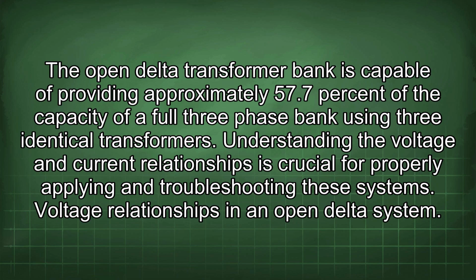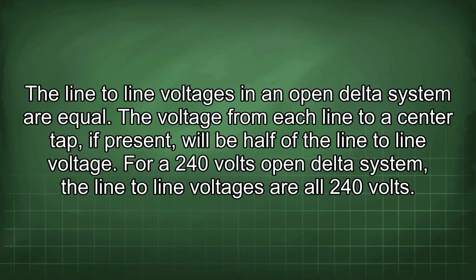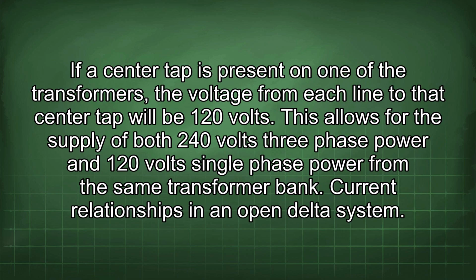Voltage relationships in an open delta system. The line-to-line voltages in an open delta system are equal. The voltage from each line to a center tap, if present, will be half of the line-to-line voltage. For a 240 volts open delta system, the line-to-line voltages are all 240 volts. If a center tap is present on one of the transformers, the voltage from each line to that center tap will be 120 volts. This allows for the supply of both 240 volts three-phase power and 120 volts single-phase power from the same transformer bank.